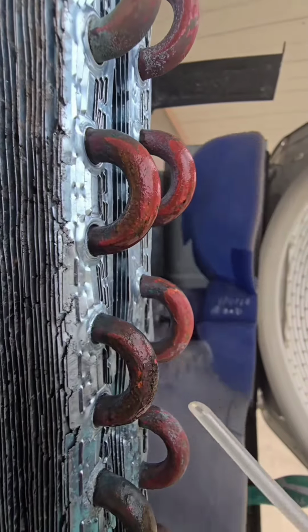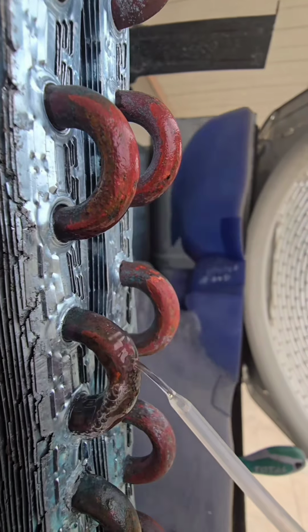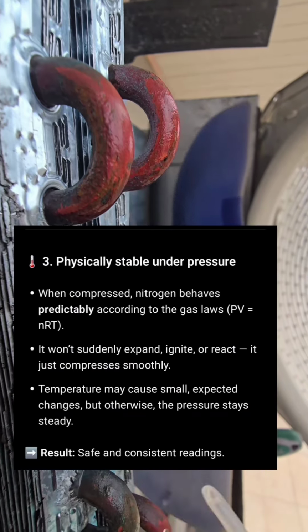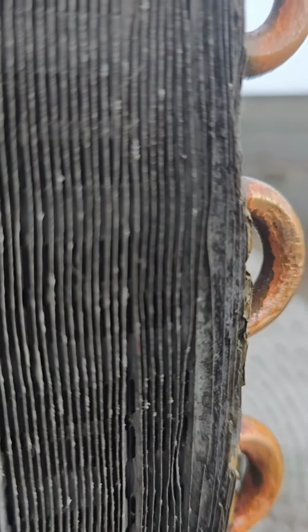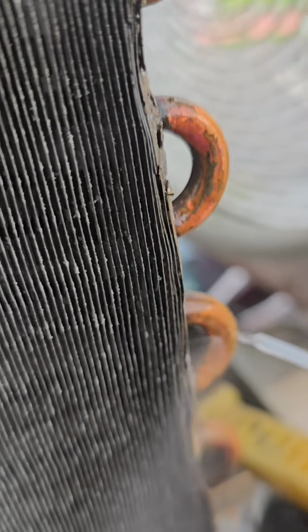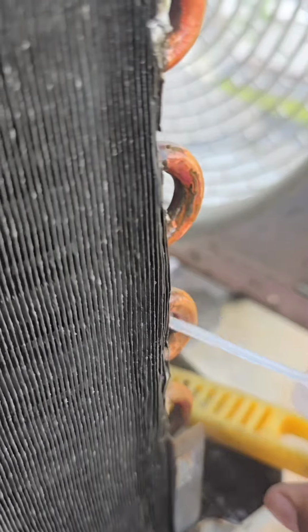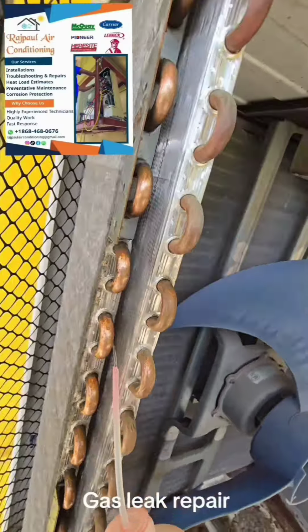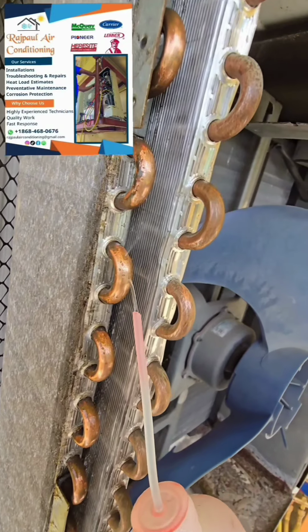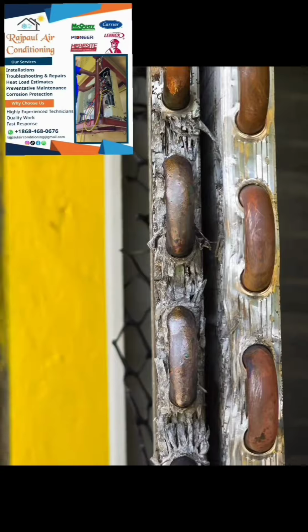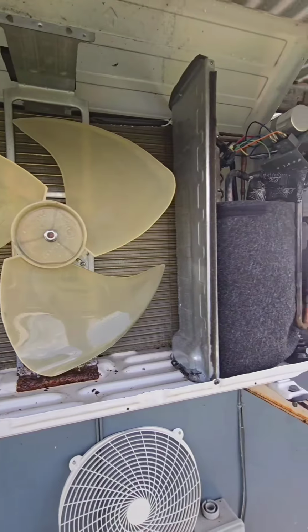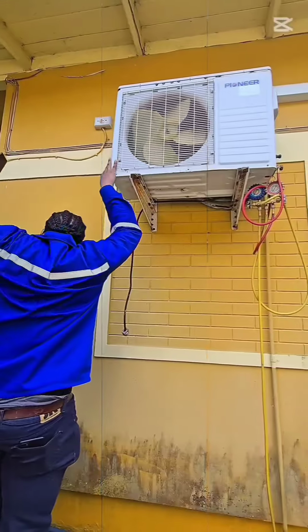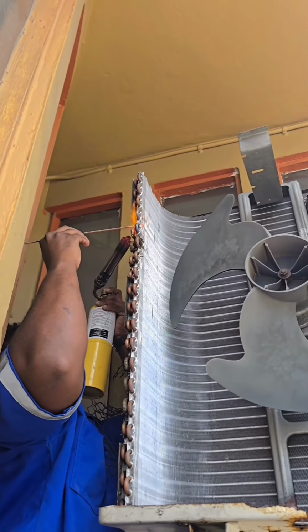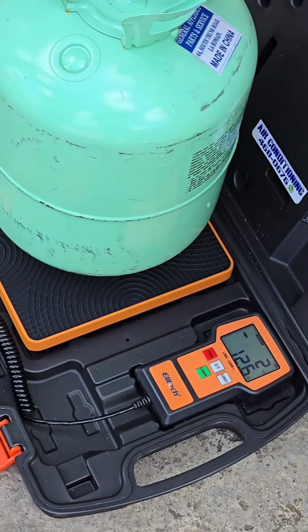And number three will be a stable pressure test. Nitrogen doesn't change pressures as easily with the change of the temperature. Compared to pressurizing with gas, for example 410A, they react to the temperature very sensitively. Meaning that with a slight increase in temperature, the pressure will go up, or with a slight decline in temperature, it will go down. So nitrogen has a more stable chemical bond that makes pressure testing more stable and easy to detect.